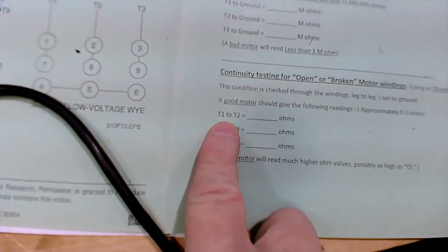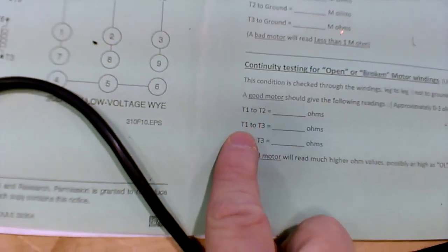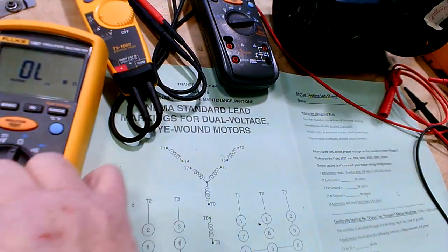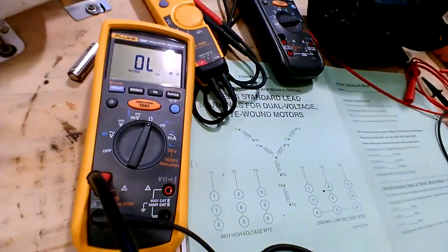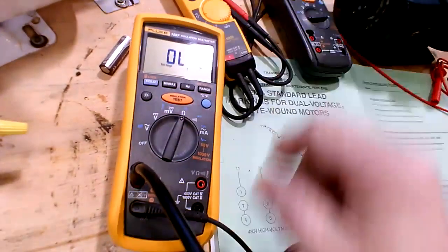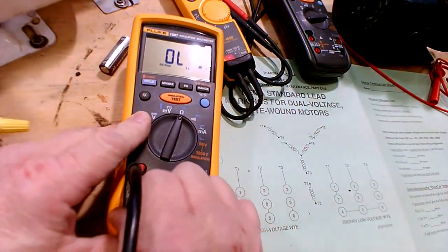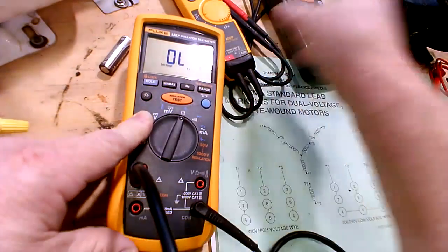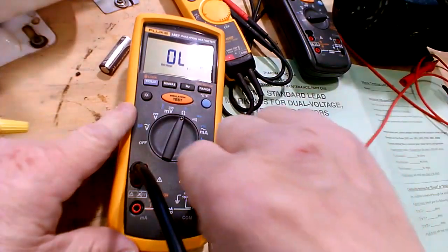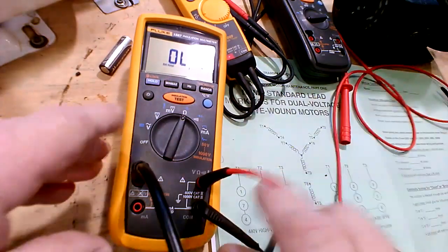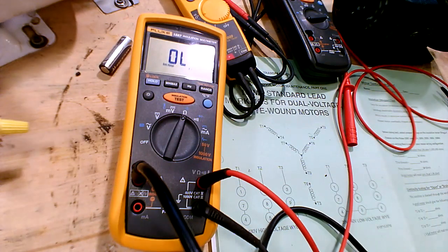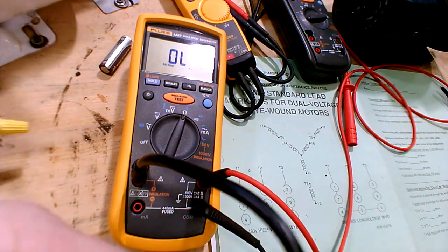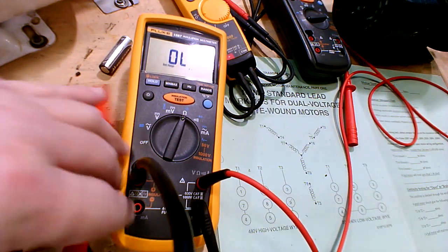The next one, we're going to check continuity through the motor from T1 to T2, 1 to 3, and then 2 to 3, going through the motor on regular ohms. So here, you go to regular ohms, you've got to move this lead back. Or you can use this meter here. If you're using this one, look, you got to move the wire back to here and get out your other regular lead, like that. No, you won't use it on doing regular ohms. Just on insulation tests.